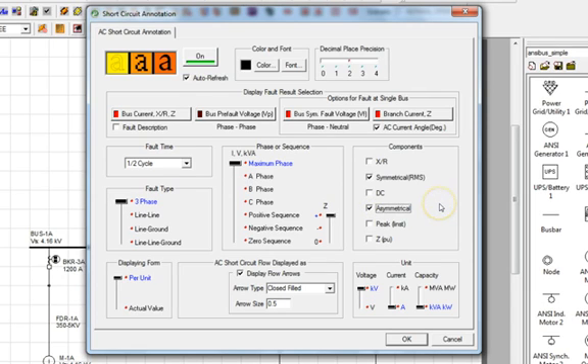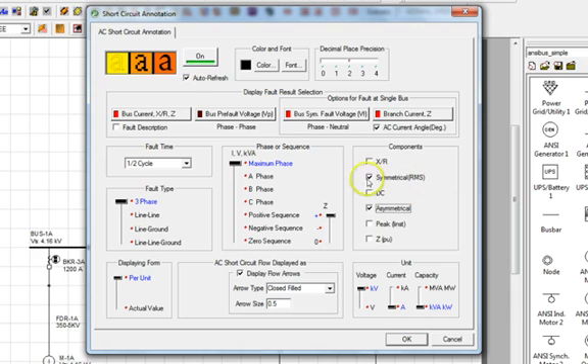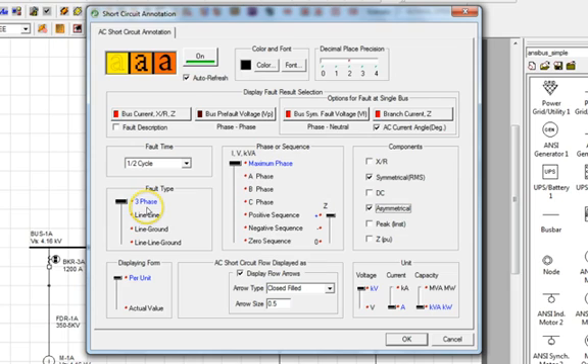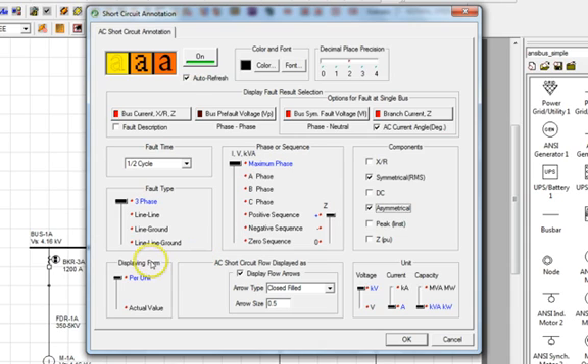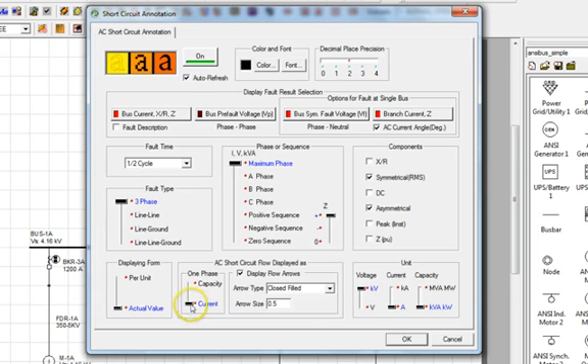So, to summarize, we will be conducting a Three Phase Short Circuit analysis, after which we will back annotate onto our Single Line Diagram the maximum Symmetrical and Asymmetrical Fault Current values for the Half Cycle Three Phase Fault Current. Next, we have to decide how to display the results. In the Displaying Form section, let's pick Actual Value instead of Per Unit and choose to display it in units of Current instead of Capacity.